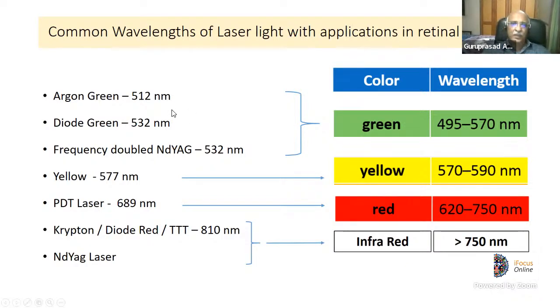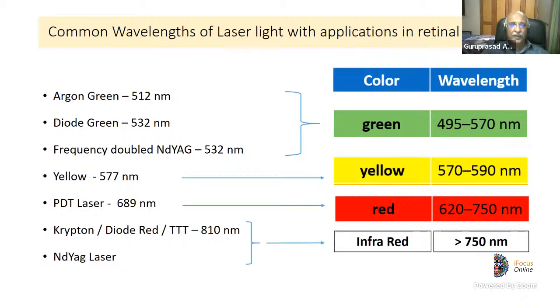The common wavelengths used in retinal disease include argon green, diode green, and frequency-doubled Nd:YAG — all in the green visible spectrum range. The yellow laser is 577 nanometers. The PDT laser is 689 nanometers (red range). Diode red (around 810 nanometers, infrared) is used for TTT, focal laser for tumors, ROP laser, and retinochoroidal coloboma-associated retinal detachment. The Nd:YAG laser is also in the infrared range.